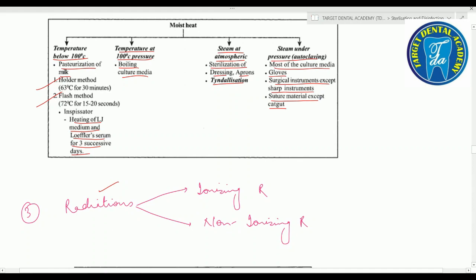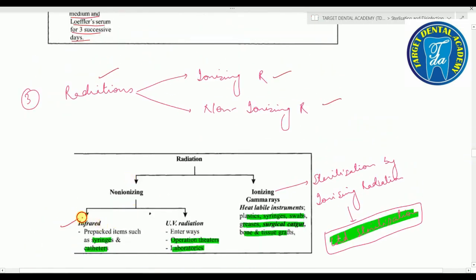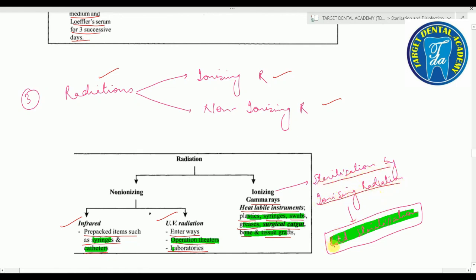Third physical method of sterilization is radiation, with two types: non-ionizing and ionizing. Non-ionizing radiation includes infrared radiation — used to sterilize pre-packed items such as syringes and catheters — and ultraviolet radiation — used for operation theaters and laboratories. Ionizing radiation, or gamma radiation, is used to sterilize heat-labile instruments like plastic syringes, swabs, greases, surgical catgut, bone, and tissue grafts. Sterilization by ionizing radiation is called cold sterilization — important.